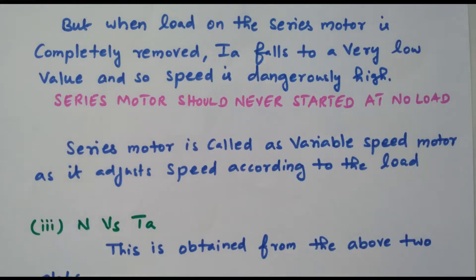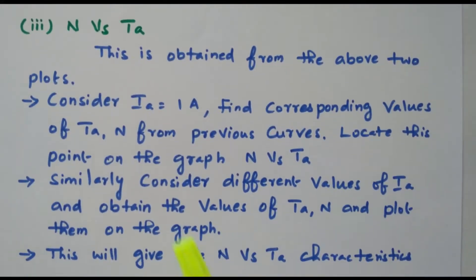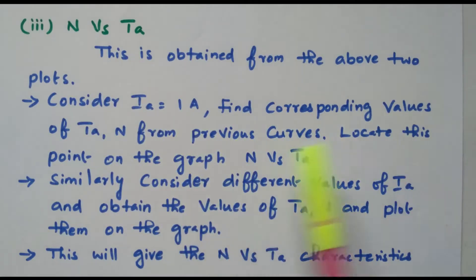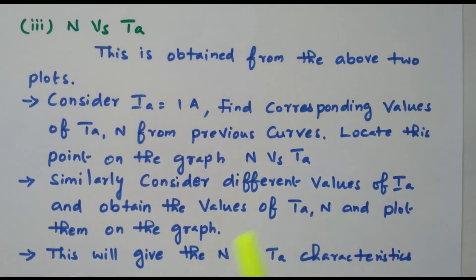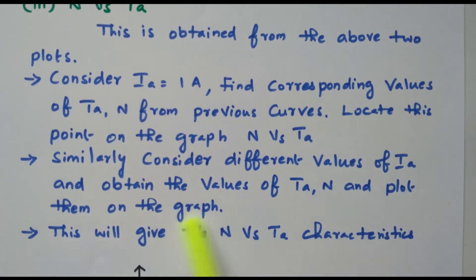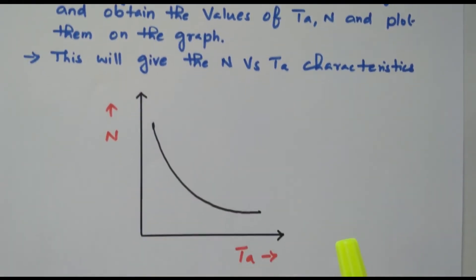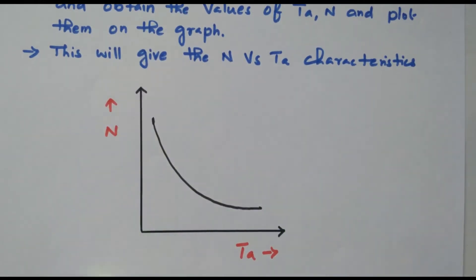Now the third characteristic: speed versus armature torque, N versus T_A. It is obtained from the above two plots. Take armature current equal to 1 ampere, find the corresponding values of T_A and N from the previous curves, and locate this point on the N versus T_A graph. Repeat for different values of I_A to obtain multiple points and plot them. This gives the N versus T_A characteristic, which shows that speed and torque are inversely proportional — when torque increases, speed decreases.